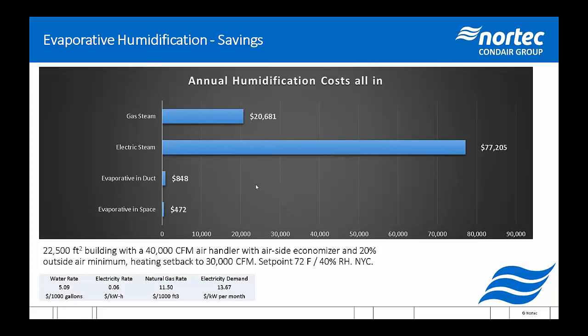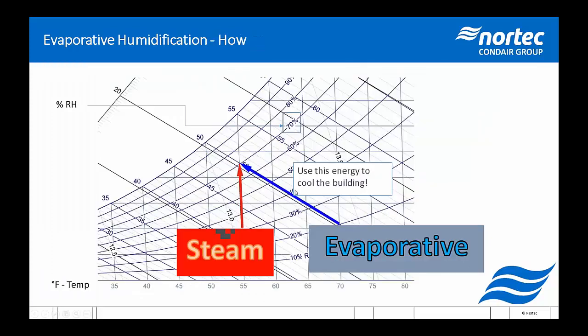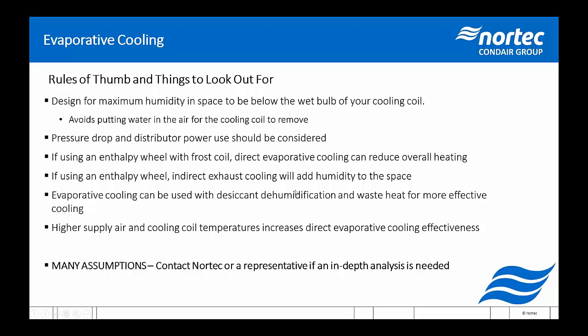Okay, I'm going to go back to where I was here. So, rules of thumb and things to look out for. I've kind of just slapped these on the screen, but we're always making sure we design the maximum humidity in the space to be below the wet bulb of the cooling coil. Basically, we don't want to humidify to the point where the cooling coil is just going to pull that water right out again. In that case, we're not saving any energy. We've just changed how we're pulling the energy out of the air, and we're wasting water.